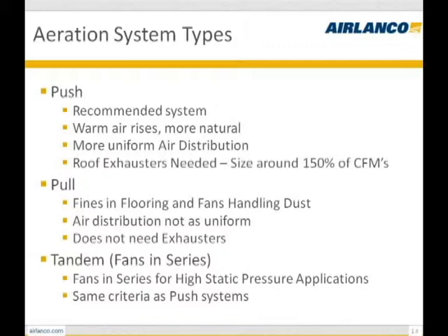But roof exhausters are really needed on this system, sized at about 150%, because as moisture comes out, you have all the moisture inside that empty space on top of the grain mass. You want to make sure you change that out. So you oversize it to get that air out, so you avoid moisture and condensation. Once again, if there's a 15 degree difference, condensation can happen, and you want to make sure that doesn't happen.